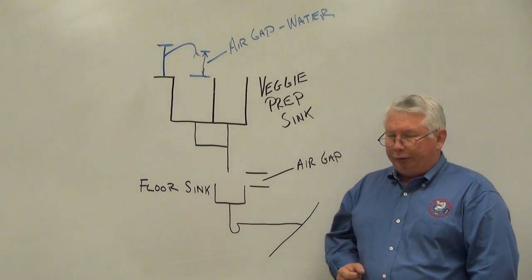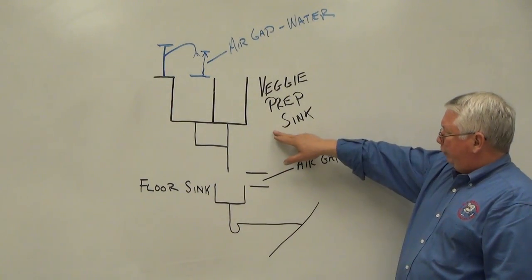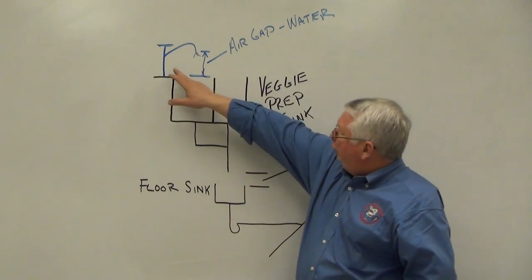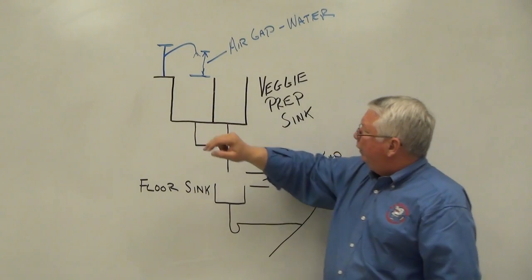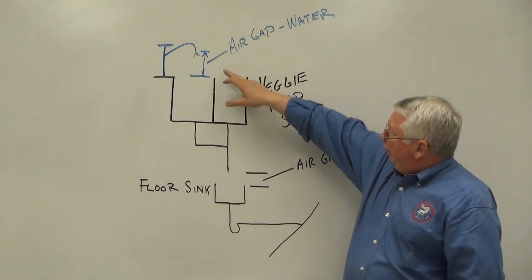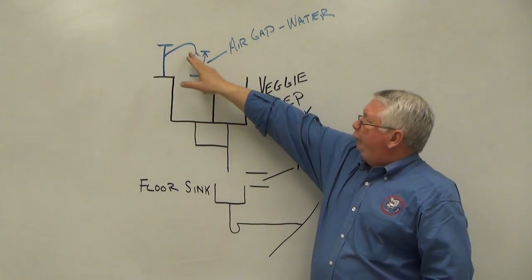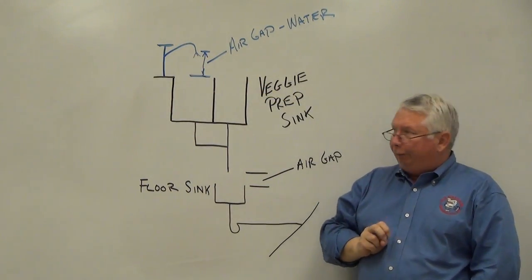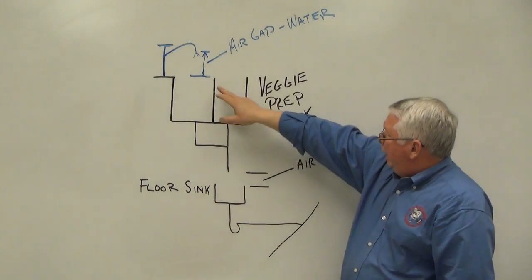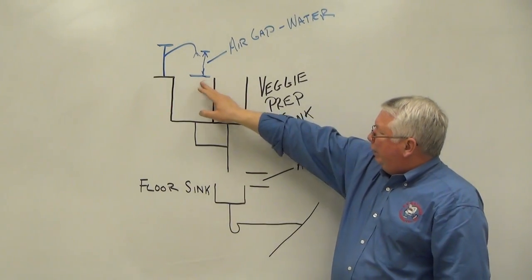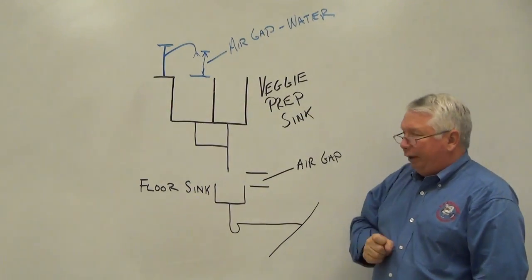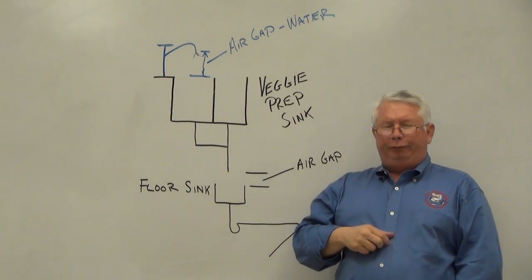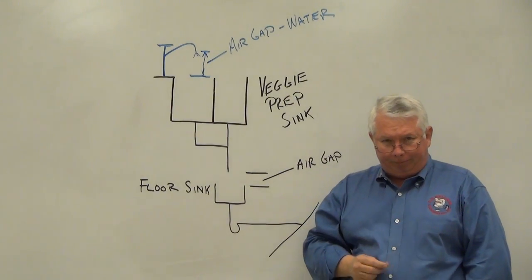In this example we have our vegetable prep sink that's being served by a faucet. The vertical distance through free atmosphere between the discharge opening of the faucet and the flood level rim of the sink is the air gap for the water distribution system.